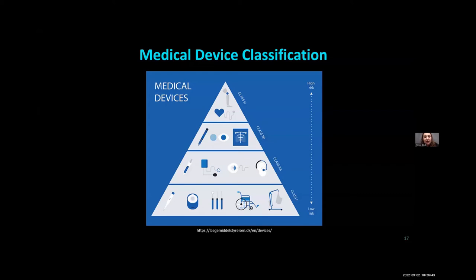In between these is class two. These tend to be things that interact with the body and can be implantable, but are perhaps implanted in lower-risk places. Eardrum grafts fall into this category because they're implanted onto eardrum tissue—it's your hearing, a very important sense, but if the eardrum graft fails, the patient isn't put into any life-altering situation.